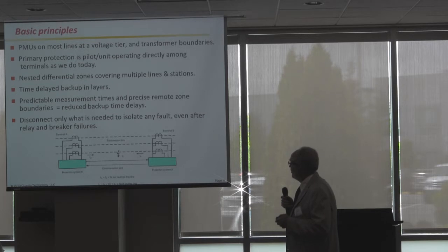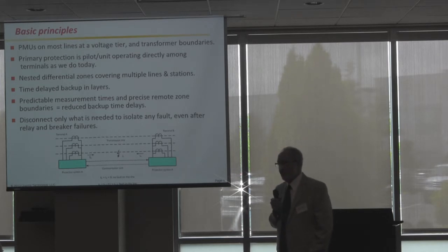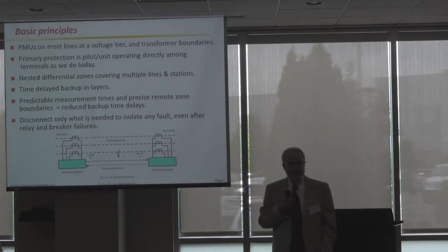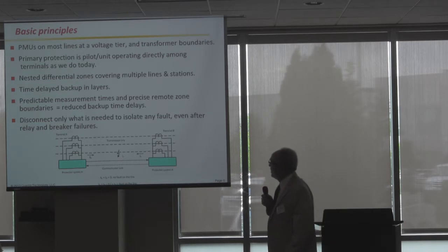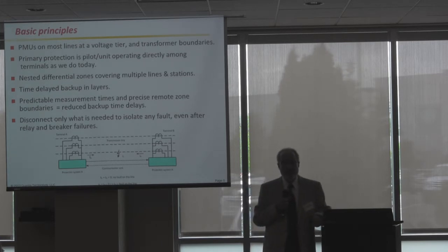It is, in particular, compared to today's distance relay backup-based methods, we get predictable measurement times and very precise, surgically precise knowledge of exactly where the problem is, and therefore exactly what to do, where to trip. We can do the right thing. Our zone 2 and zone 3 relays don't always operate so selectively. And we get predictable measurement times, so it's actually possible to talk about reducing backup clearing times, a great benefit to system stability improvement.